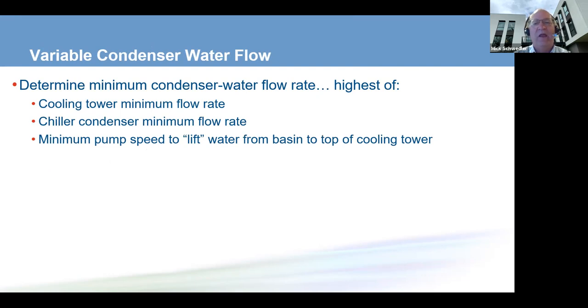The first is, what's the minimum flow rate for the cooling tower? And frankly, that's probably the biggest limitation in most applications. If you go below the tower's minimum flow rate, you get poor heat transfer. Your leaving water temperature goes up, but even worse, you get some splash from the wetted portions of the tower to the dry portions, and you get scaling. Scaling is really hard to clean up on cooling towers.